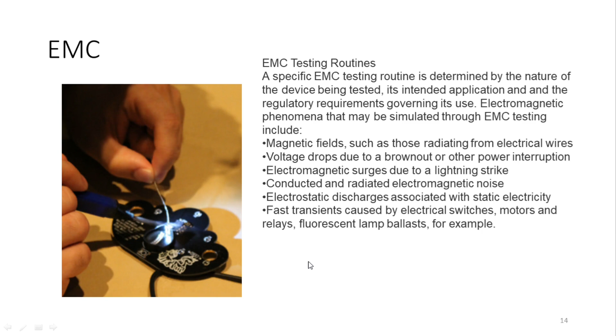EMC testing routines will majorly follow testing of magnetic fields, voltage drops due to brownout or other power interruption, electromagnetic surges due to lightning strike, conducted and radiated electromagnetic noise, electrostatic discharges associated with static electricity, and fast transients caused by electrical switches, motors and relays, fluorescent lamps, etc.